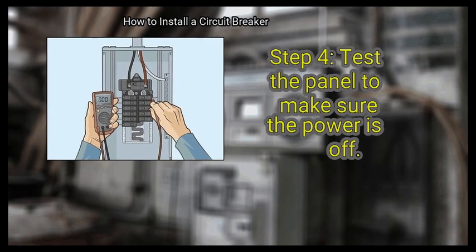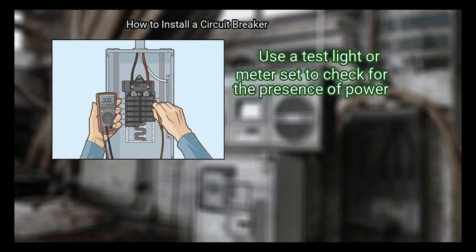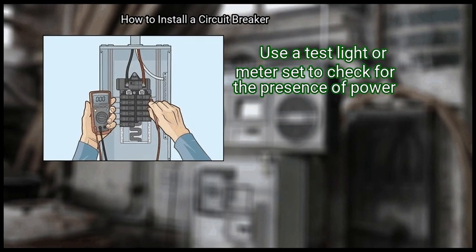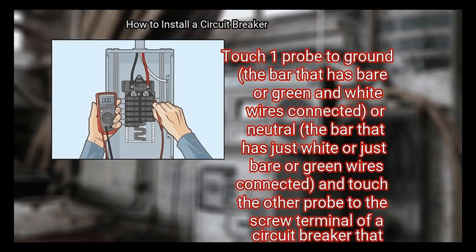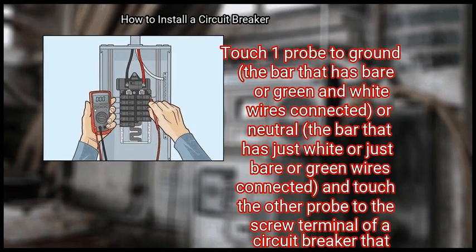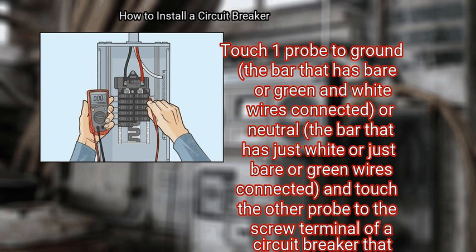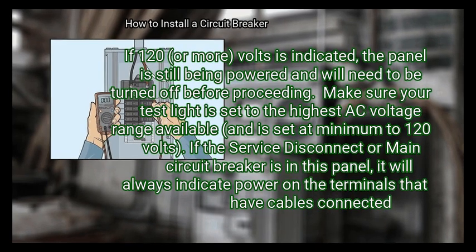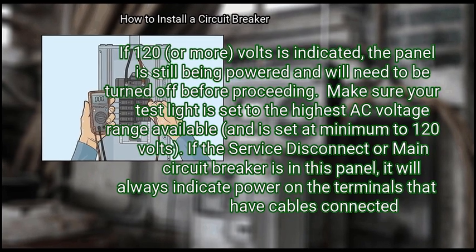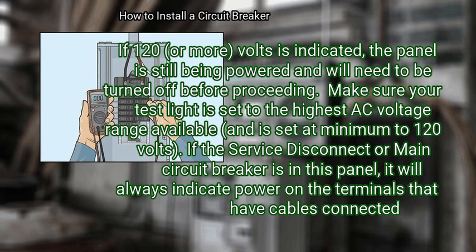Step 4. Test the panel to make sure the power is off. Use a test light or meter set to check for the presence of power. Touch one probe to ground, the bar that has bare or green and white wires connected, or neutral, the bar that has just white or just bare or green wires connected. And touch the other probe to the screw terminal of a circuit breaker that has a black, red, or blue insulated wire connected. If 120 or more volts is indicated, the panel is still being powered and will need to be turned off before proceeding.